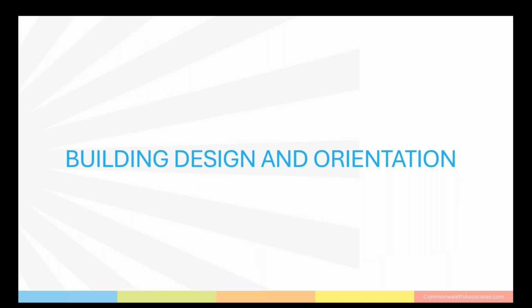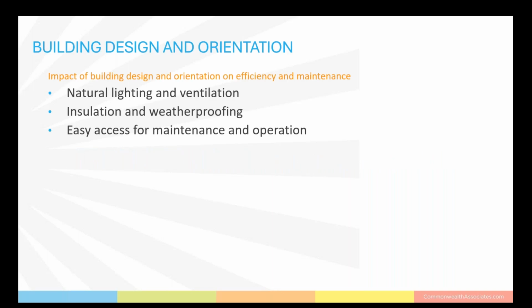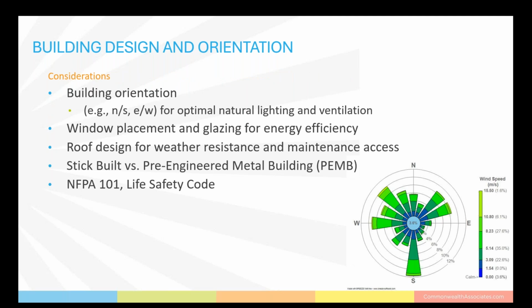Next, I'll get into some of the considerations for building design. While a CHP can thrive outside, many clients want their plant to be enclosed. This slide is a short list of some of the basics that need to go into building design. Light wall design and things like man doors, roll-up doors, removable panels for easy access for maintenance and operation. Considerations for building design are how the building is oriented on the site, whether it sits north-south or east-west. If it's possible to place windows or translucent panels for natural lighting, what type of roof design it will have. And one aspect that often doesn't get enough thought at the beginning is whether or not it's stick-built versus pre-engineered. And finally, during the process of the layout within the building, the designers need to consider that the NFPA codes for life safety egress are met.